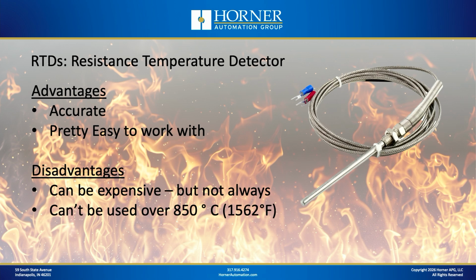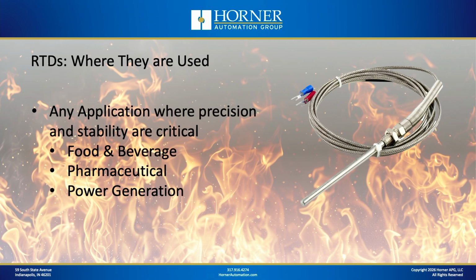Okay. Now let's pivot to RTDs, and RTD stands for resistance temperature detector. In a couple slides, it'll be pretty obvious how they work. But the advantages of RTDs are they are accurate and they are stable and they're easy to work with, relatively speaking, compared to thermocouples especially. However, they do have some disadvantages. Sometimes they can be a little bit expensive, but not always. And they do have a more limited temperature range than thermocouples do, and they don't respond quite as fast. So that's something to keep in mind with RTDs.